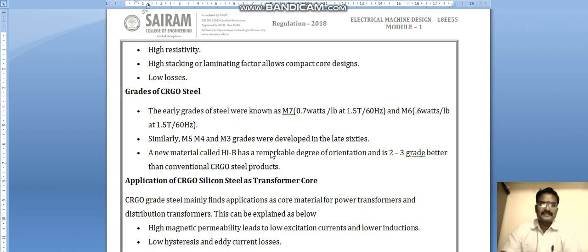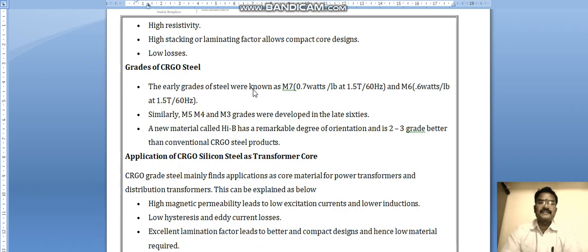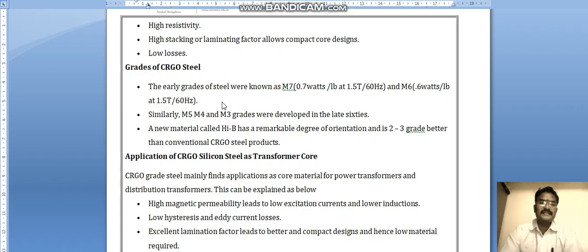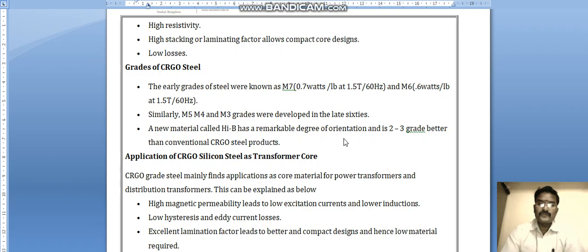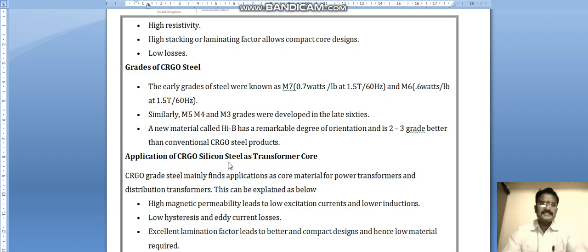The early grades of CRGO steel were known as M7, rated at 0.7 watts per pound at 1.5 Tesla at 60 Hz. Similarly, M5, M4, and M3 grades were developed in the late 1960s. A new material called HiB has a remarkable degree of orientation, 2 to 3 grades better than conventional CRGO steel products, further reducing losses.